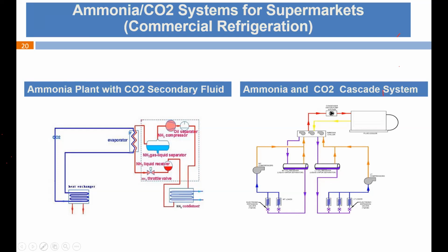I'll just put the pointer on. There is a low temperature compressor, this is the medium temperature compressor, and there is ammonia refrigerant. This type of cascade system is adopted in the case of a CO2 ammonia system. And CO2 can also be used as a secondary refrigerant, where the main chiller is an ammonia chiller, and CO2 is used as a secondary fluid.